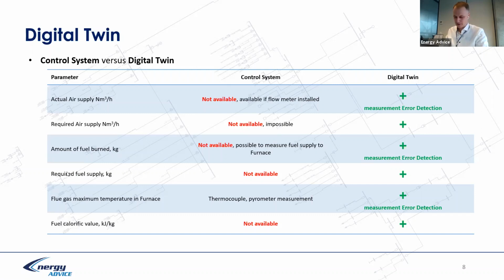Required fuel supply is interesting because fuel humidity is changing over time. In one hour you can have fuel with, for example, 40% water content, and in another hour you can have 35 or 45% water. And in fact, the required fuel calorific value changes. So we need to understand what fuel is required to supply each second, each minute. In fact, in the control system it is not available, because the control system controls fuel supply according to other variables like flame temperature, flue gas temperature, etc., heat consumption, steam consumption, output. But the digital twin can evaluate the required fuel supply.